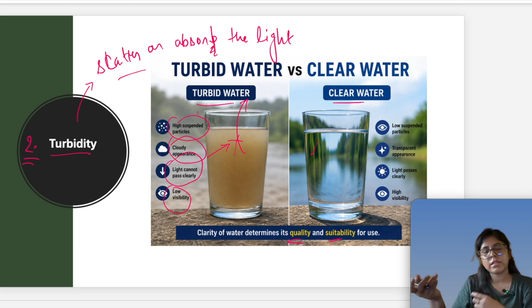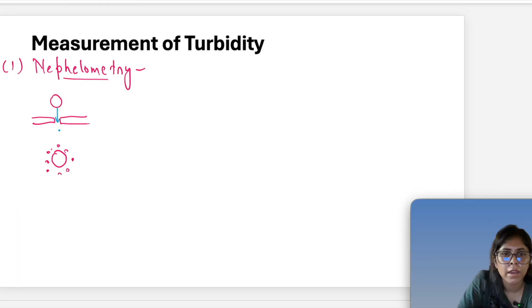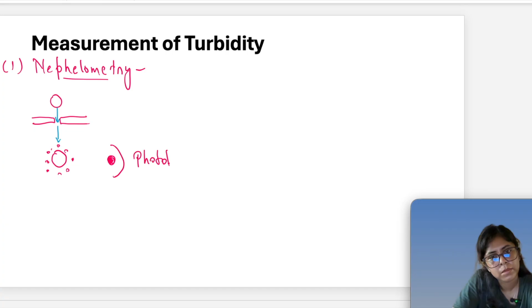So we have measurement of turbidity in the form of, first, nephelometry. The concept behind nephelometry is, see, we have a light source and then we have a slit. Then after that we have our turbid sample, which has turbidity in it. The light source throws light like this. And we put our detector, or phototube, as we call it, at 90 degrees. This is the phototube or detector, this is our light source, this is the slit, and this is our water sample.